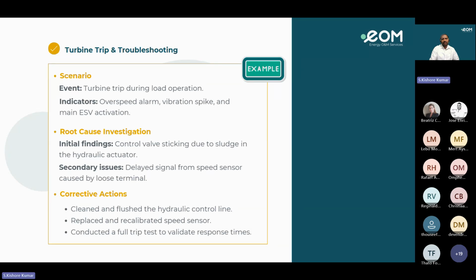In this scenario we can clearly understand the root cause investigation: the control valve is sticking due to sludge in the hydraulic actuators. Yes, because sometimes if we do not perform the lube oil analysis, and the NAS value is higher and the water parameters are on the higher side, and we do not check the oil properties, that will cause the control valve sticking.